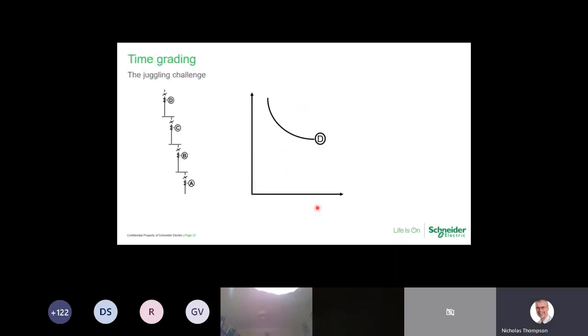Now then, when we start to look at various different circuit breakers and various different curves, we've got an example of 4 circuit breakers with 4 protection relays. Starting at the top with D, that's our supply, so that could very well be our DNO circuit breaker, which will have its own tripping characteristics, its own curve, its own time delay. So that is our starting point. And when we start to look at C, we've got that curve there, so we can sit that nicely there. When we move to B, we've got that one there. So on the face of it, everything looks okay.